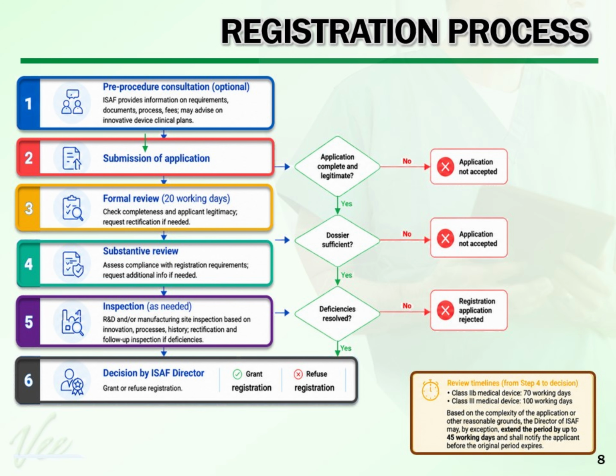Here is the medical device registration process in Macau. Step 1 is an optional pre-procedure consultation, where ISAF provides information on requirements, documents, process, fees, and may advise on innovative clinical plans. Step 2 is submission of the application. Step 3 is a formal review, typically completed within 20 working days. Step 4 is the substantive review. Step 5 is inspection. Step 6 is the decision by the ISAF director, who grants or refuses registration. From substantive review to decision, the timeline is 70 working days for Class 2B devices and 100 working days for Class 3 devices, with a possible extension of up to 45 working days for high-complexity cases.